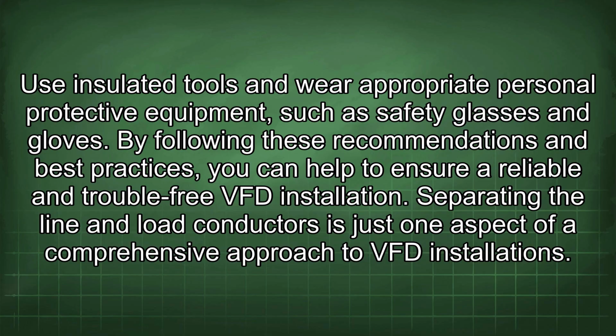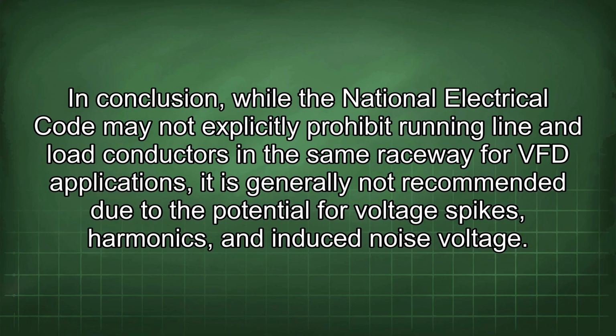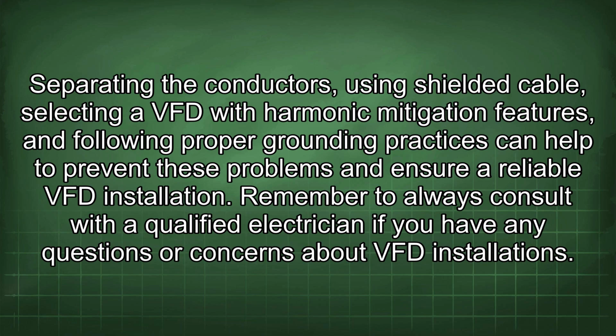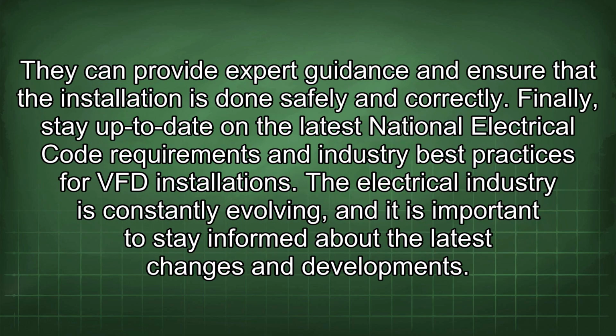Separating the line and load conductors is just one aspect of a comprehensive approach to VFD installations. In conclusion, while the National Electrical Code may not explicitly prohibit running line and load conductors in the same raceway for VFD applications, it is generally not recommended due to the potential for voltage spikes, harmonics, and induced noise voltage. Separating the conductors, using shielded cable, selecting a VFD with harmonic mitigation features, and following proper grounding practices can help to prevent these problems and ensure a reliable VFD installation. Remember to always consult with a qualified electrician if you have any questions or concerns about VFD installations. They can provide expert guidance and ensure that the installation is done safely and correctly.